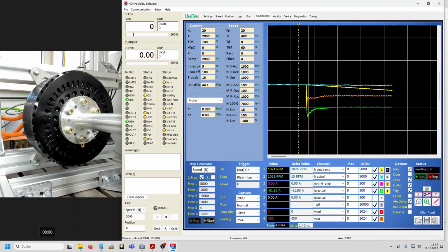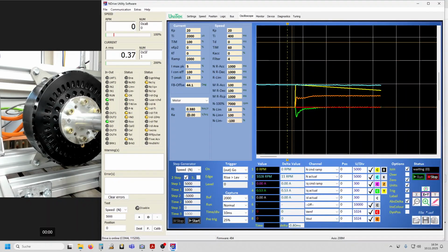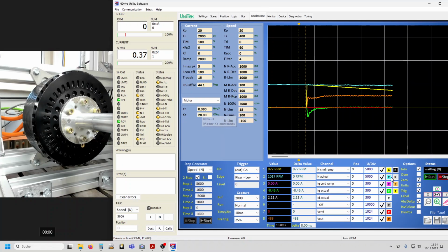That is because the PI controller is lacking the BackEmf pre-control it requires to smoothly enable on a spinning motor using torque control. So let us test now. We're gonna provide a small KE factor of, let's say, 20 volts per 1000 RPM. I'm gonna make this a little bit bigger so we can see this a little bit better. And then we just repeat.